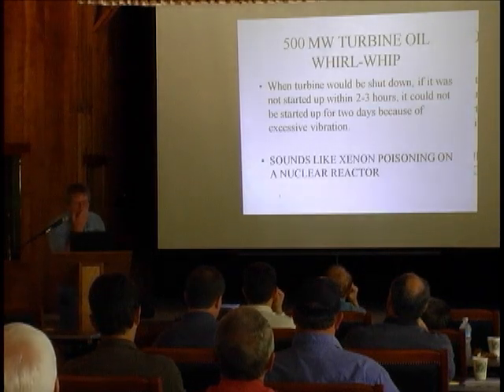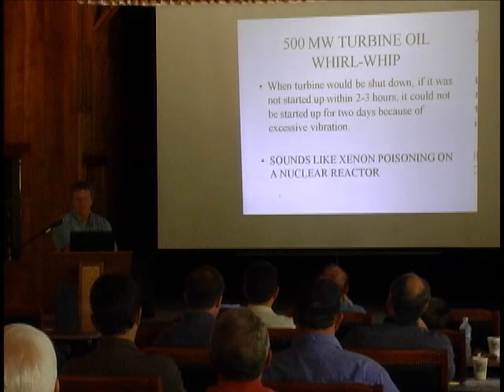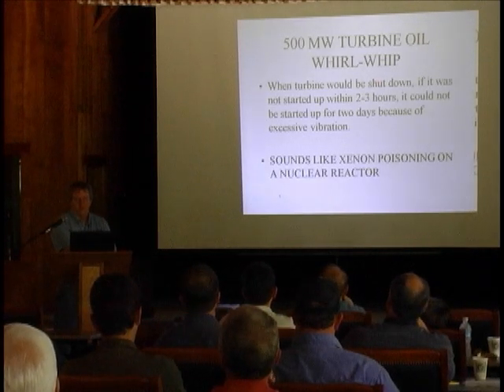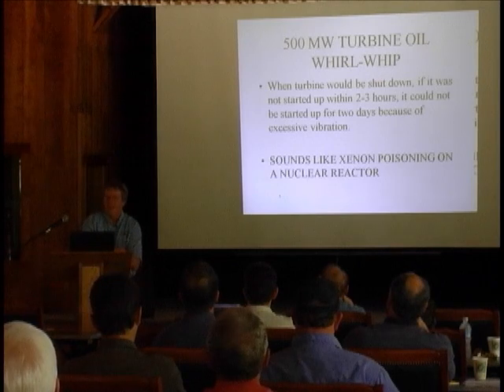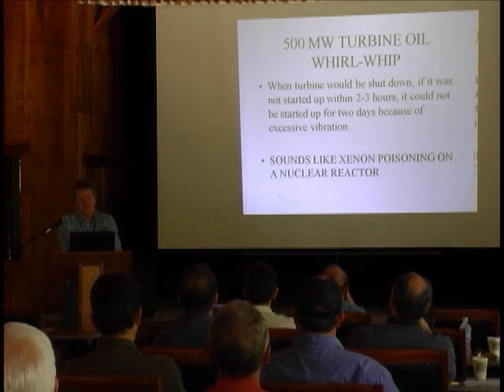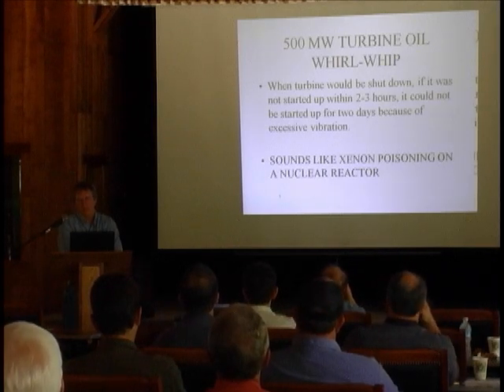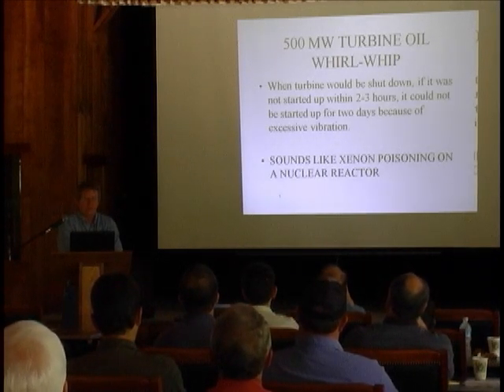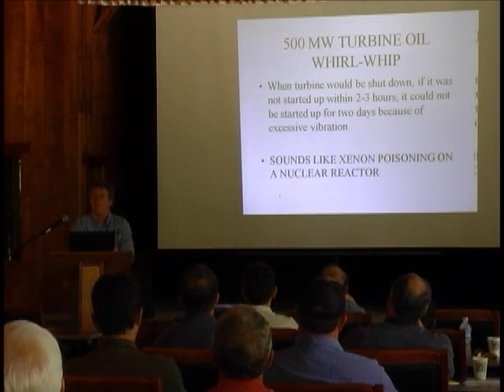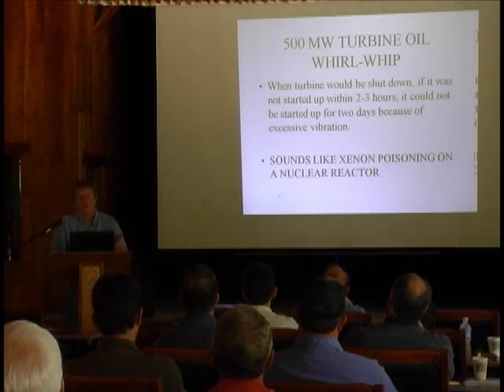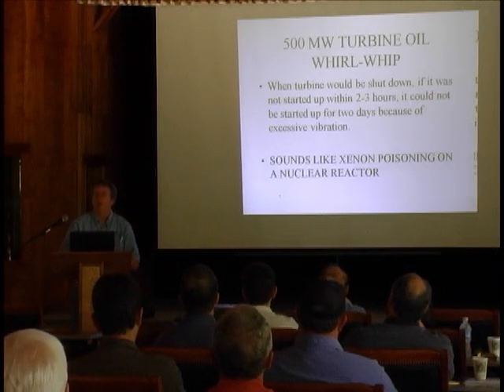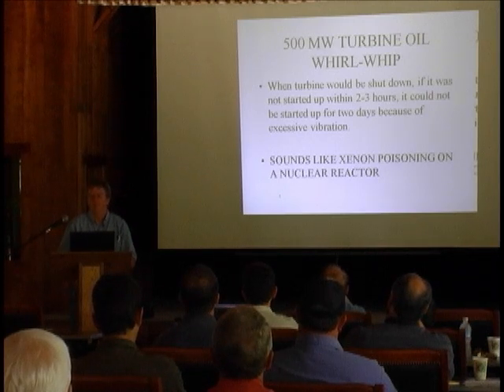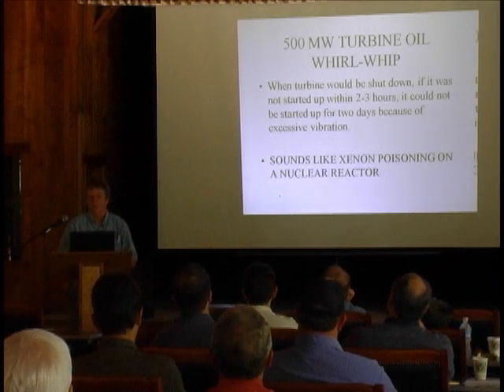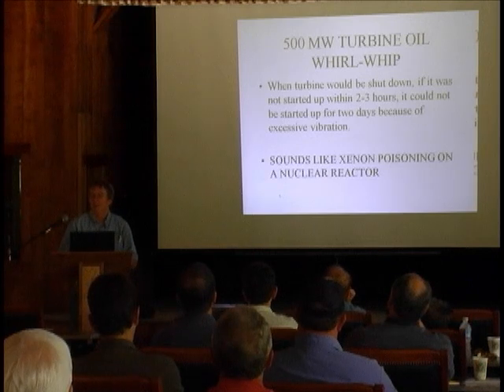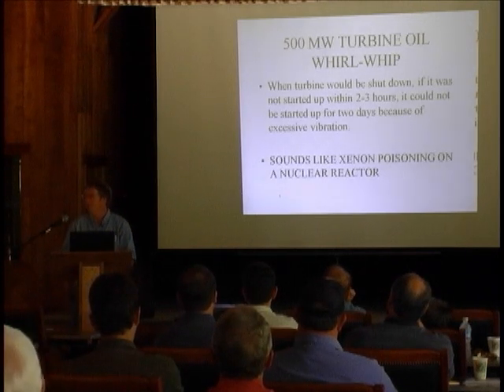Okay. So we're going to go into even more weirdness. I don't know whether I've been blessed or cursed by this business, but I seem to always end up with this weird, odd stuff. And this was a turbine, a 500 megawatt turbine, and they would shut it down. They'd be going along, they'd have a problem, and it would trip. And if they started the turbine back up, it would start up fine. But if they waited more than a couple hours, you couldn't start it back up. You had to wait a couple days to start it up. So if you didn't start it back up within 2 or 3 hours, you weren't going to get it back for 2 days.